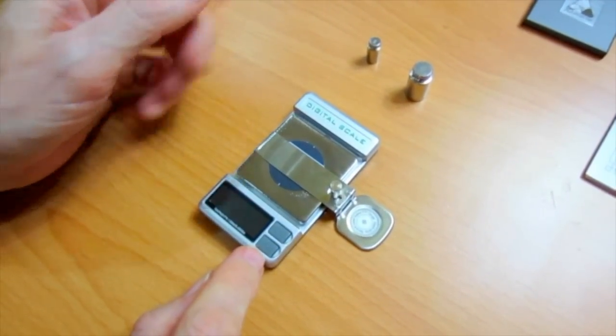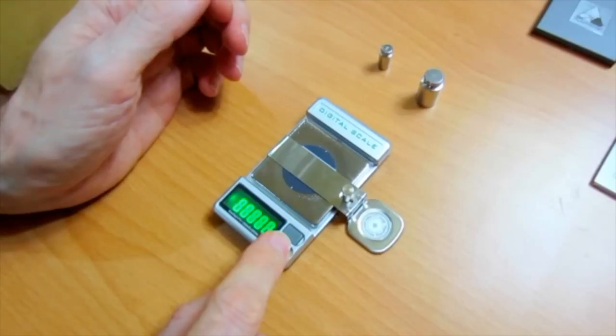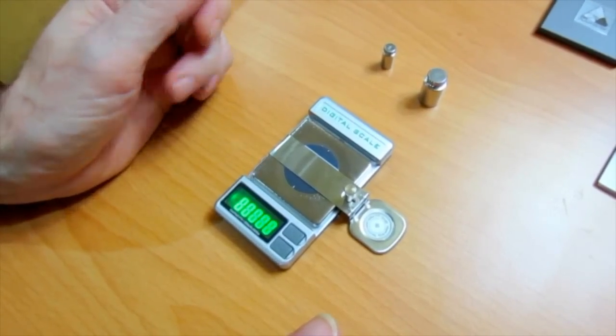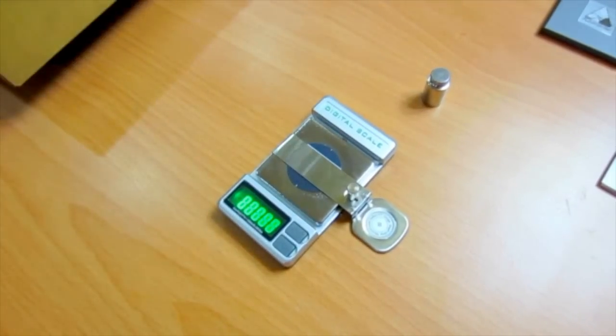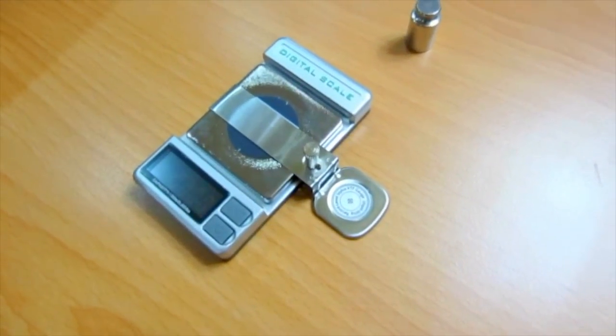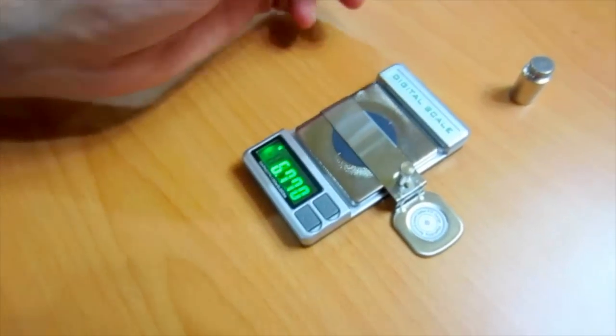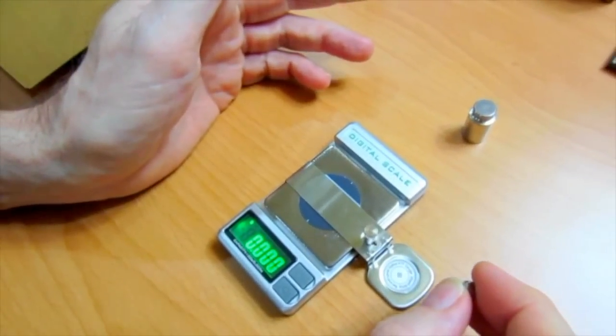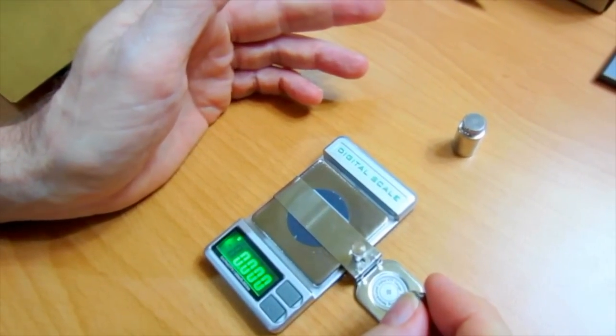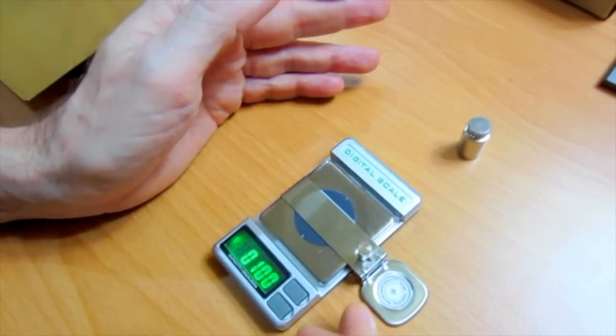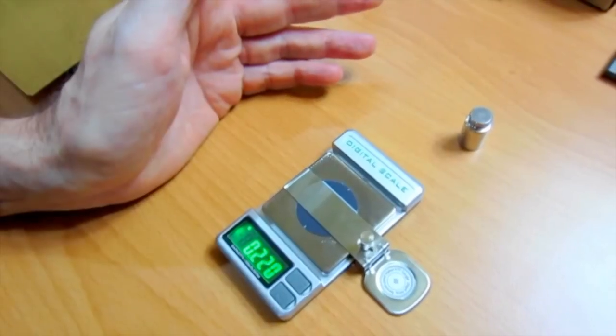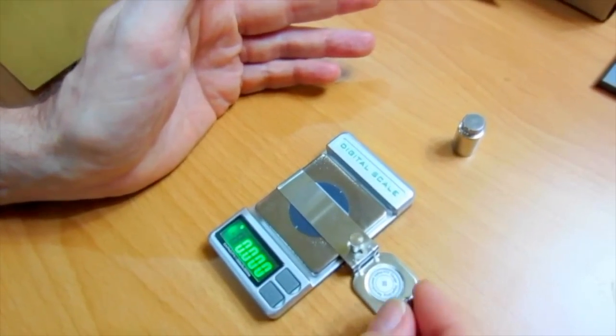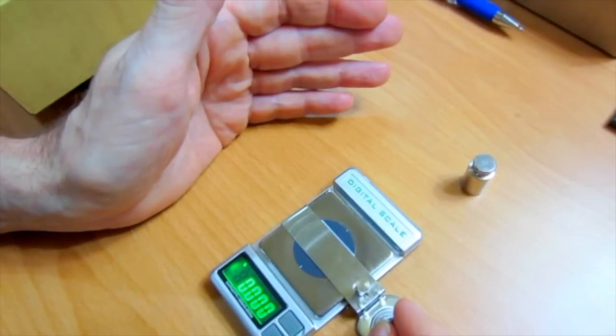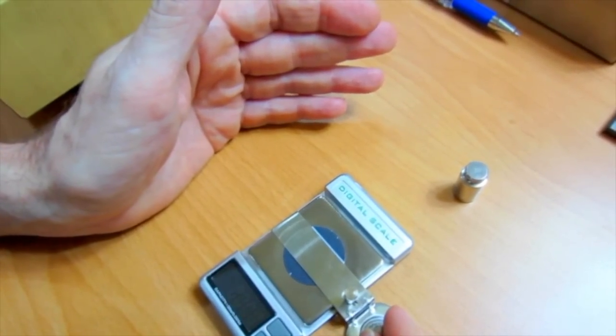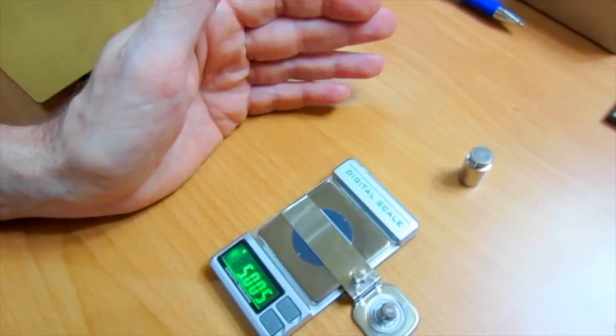Okay, with the arm on, let's go through a calibration now. And again, this was previously calibrated with 20 grams. Let's check the calibration with the 5 gram mass. Again, when you're calibrating, make sure that you've got a, as I mentioned earlier, stable level environment, table rather, and make sure you're not breathing on it because even small air currents are enough to affect the calibration. All right, just simply blowing on it, or if you're talking, let's go ahead and see if we're okay or if we need to calibrate or not.